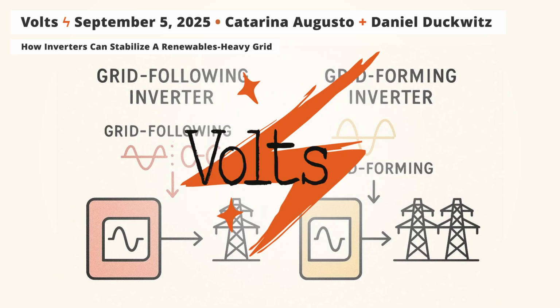We would probably not call them grid forming, but rather advanced inverters? Inverters plus. We call it transient voltage control for PV inverters. That means they behave like a voltage source, but only regarding reactive power, not regarding inertia. So there's some middle ground between grid following and grid forming, and this is what a PV-only plant can do.